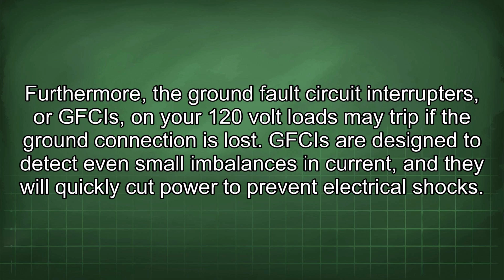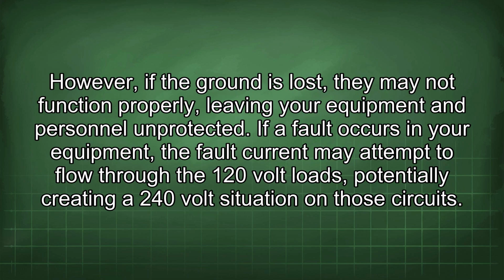Furthermore, the ground fault circuit interrupters, or GFCIs, on your 120-volt loads may trip if the ground connection is lost. GFCIs are designed to detect even small imbalances in current, and they will quickly cut power to prevent electrical shocks. However, if the ground is lost, they may not function properly, leaving your equipment and personnel unprotected.